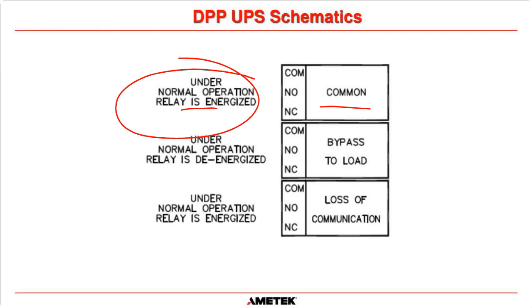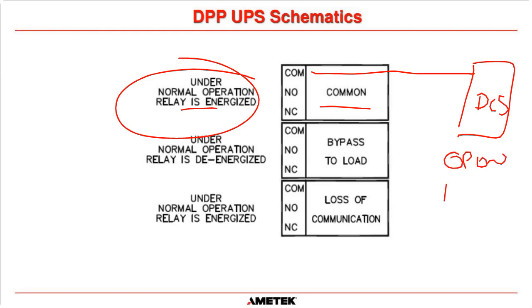Now, most plants will connect their alarm signals back to their DCS system in what's called a fail-safe mode of operation. What they're looking for back, so if we connect our common back to your DCS system, is we want an open contact for a fault. And the reason we have that is if somebody comes along and cuts that cable, this contact to the DCS goes open, and you will get an alarm if somebody cuts those cables. So we want a normally open alarm to describe a failure.